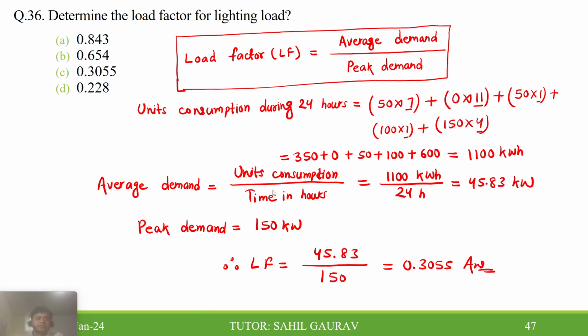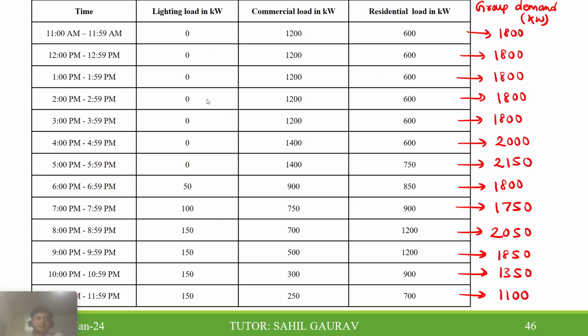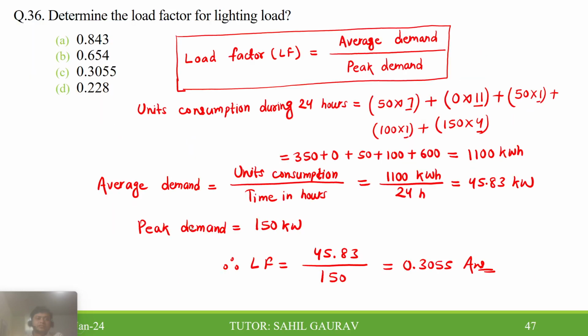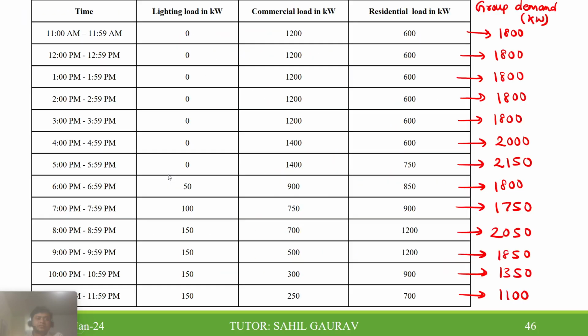So if you do the simplification, it will give you 1100 kilowatt hour. So average demand will be divided by time in hours, so it will give you 45.83 kilowatt. Now for the peak demand for lighting load, you have to see what the peak demand for lighting load is. It is 150 kilowatt, if you see the table.